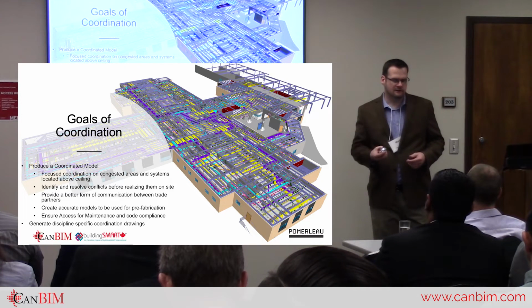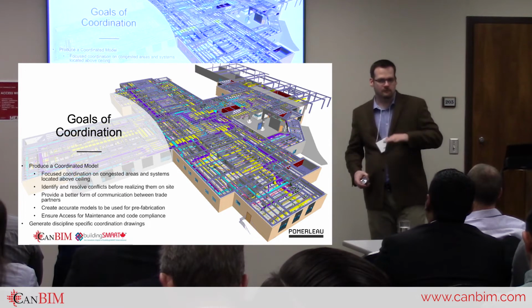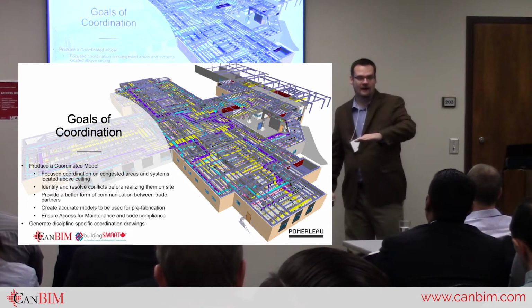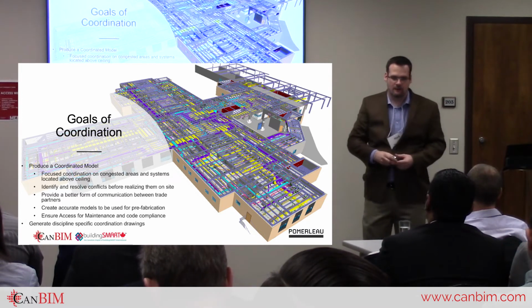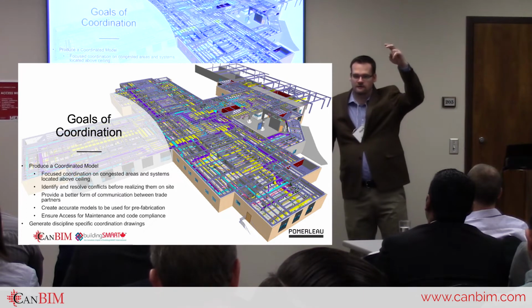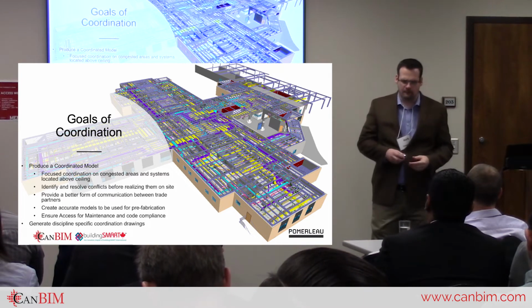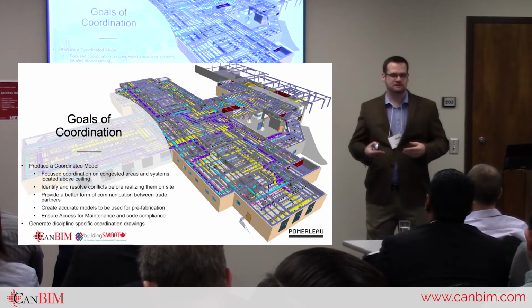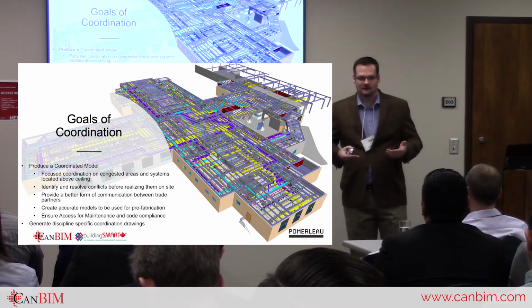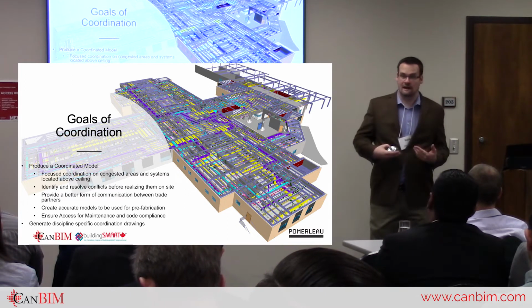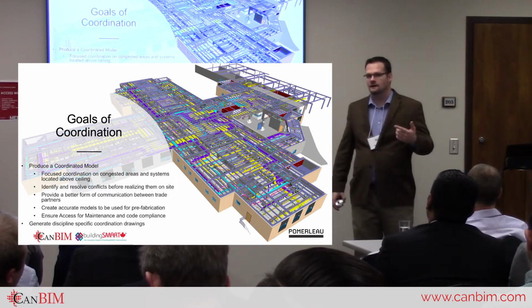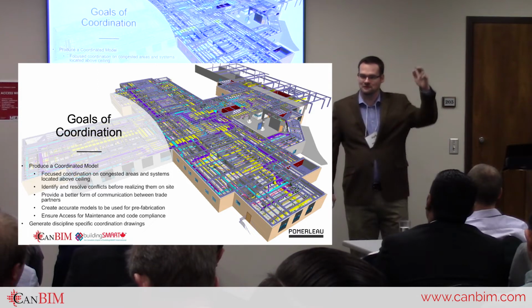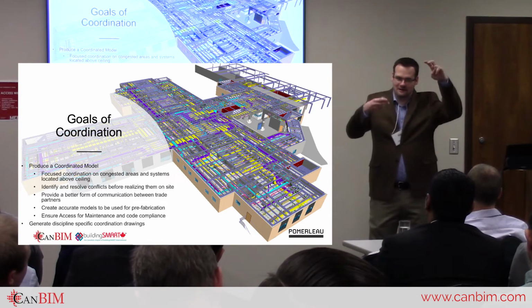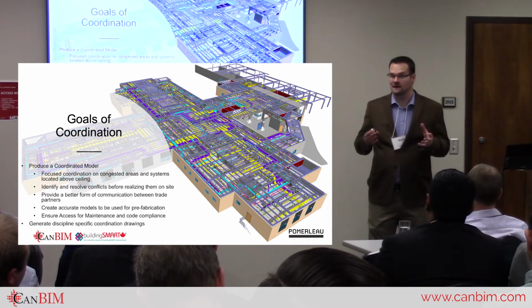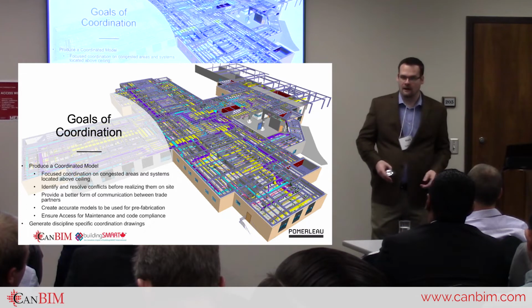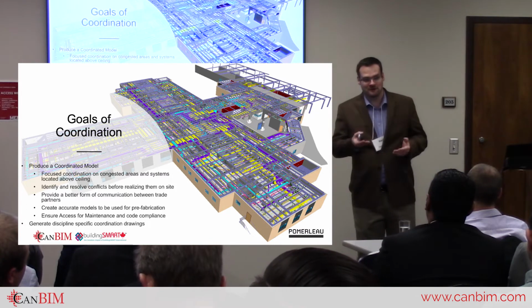One example here: we had fire protection about this high, then duct on top, a big duct about this size in the model, and 2 water pipes above it plus structural steel. The problem was the fire protection guy was saying to the duct guy that your system is interfering with mine. This was really problematic, and eventually it came to me. I looked into it and realized that in the model, somebody hadn't modeled the insulation for those 2 little water pipes above, which pushed the duct down into the fire protection. We were able to identify that and solve it by rerouting the water pipe. It turned out the fire protection pipe was never in the way of the duct.